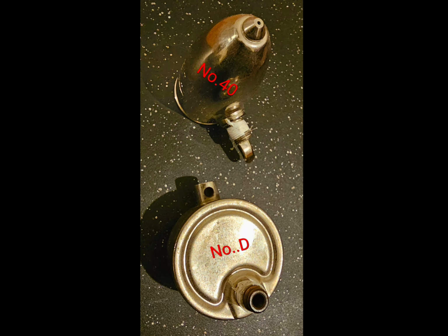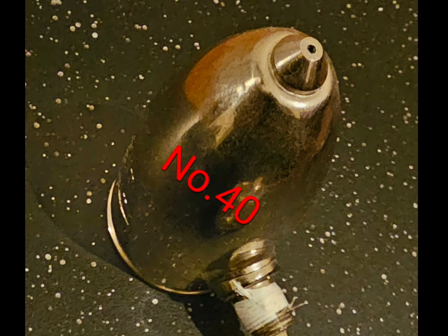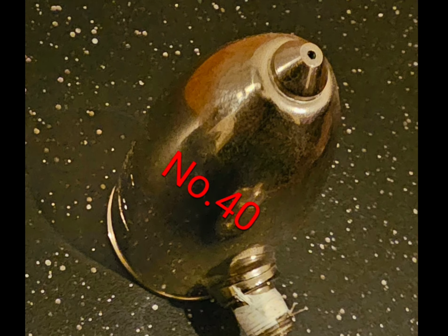Now, how could this be possible according to what he's mentioning about the drop away pressure and how you need this stuff set up? There's no way that I could run a system at 8 psi and this vent still stays open. There's no way. If what he was saying was true about this particular vent, then there's no way that I can get away with doing that. And I did this on a regular basis, testing these air vents.